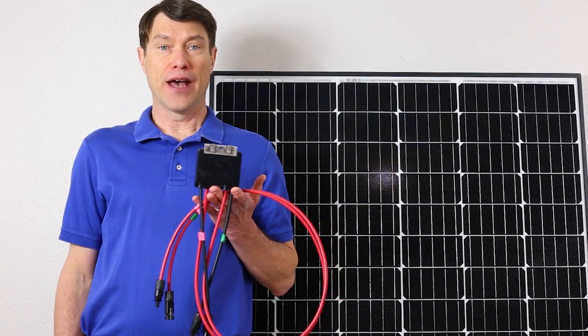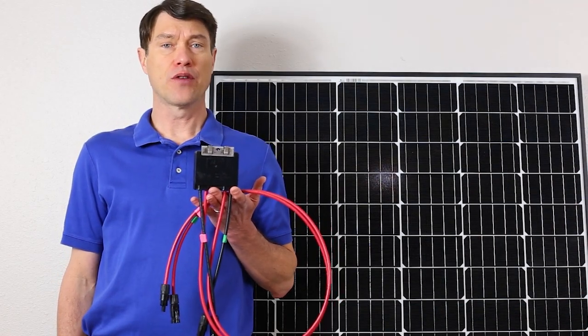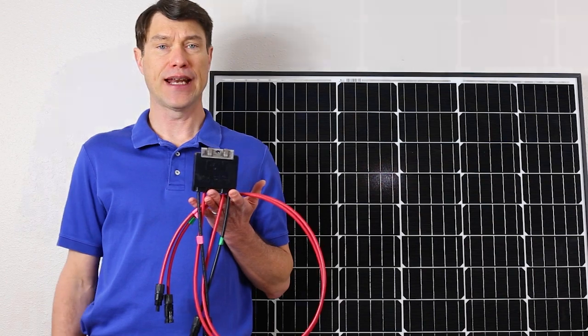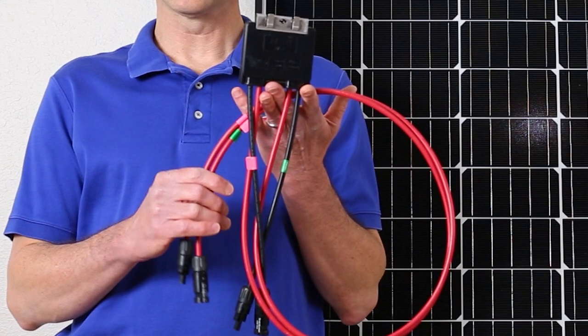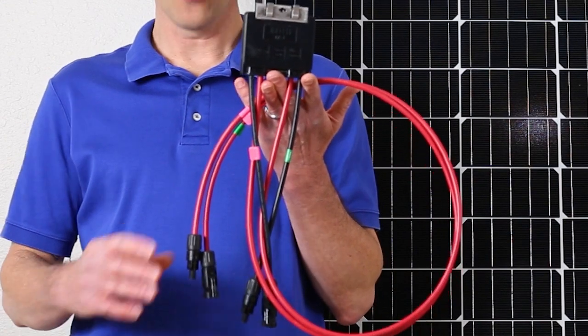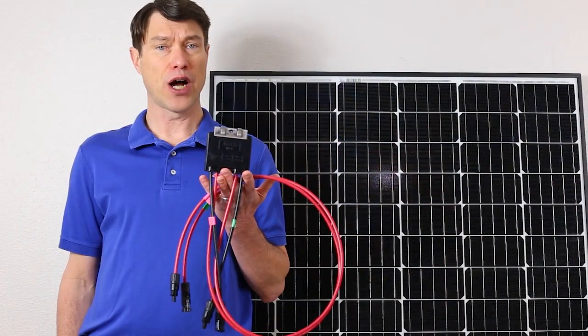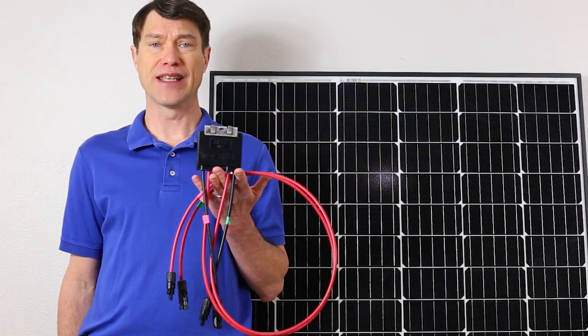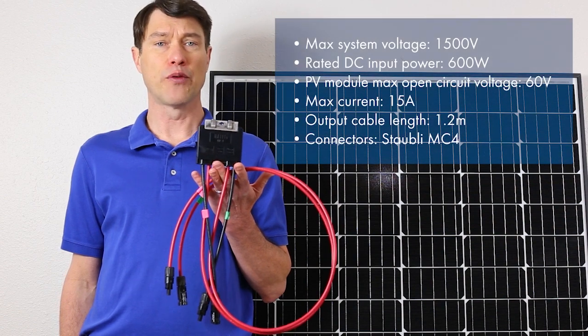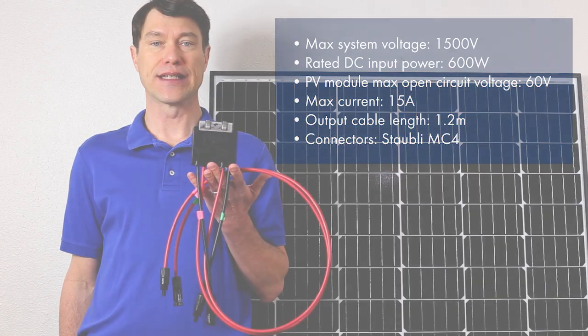The JMS-F device works with modules up to 600 watts, 60 volts, and 15 amps. The red output leads are 1.2 meters in length, and all connectors, output, and input are true MC4. Please note that every module in the array must be equipped with the JMS-F device to meet all of the rapid shutdown requirements of the 2017 NEC.